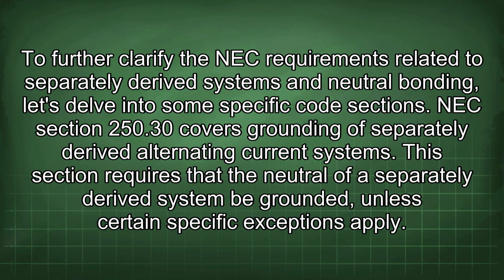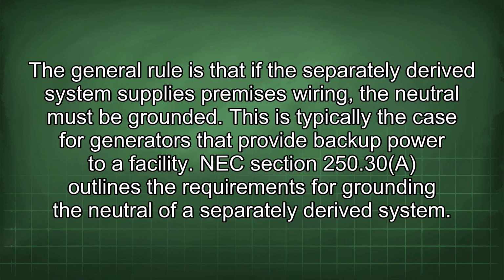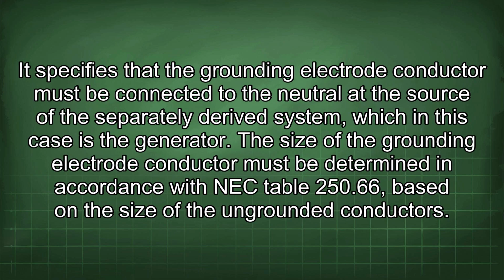To further clarify the NEC requirements related to separately derived systems and neutral bonding, let's delve into some specific code sections. NEC Section 250.30 covers grounding of separately derived alternating current systems. This section requires that the neutral of a separately derived system be grounded, unless certain specific exceptions apply. The general rule is that if the separately derived system supplies premises wiring, the neutral must be grounded. This is typically the case for generators that provide backup power to a facility. NEC Section 250.30 outlines the requirements for grounding the neutral of a separately derived system. It specifies that the grounding electrode conductor must be connected to the neutral at the source of the separately derived system, which in this case is the generator.